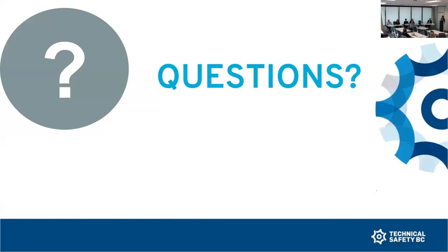So all of those are big questions. And how do you put an effective overall safety program in place so that your ventilation, your detectors, your hazard assessment, and your emergency procedures that allow or restrict entry into a space that's known to have ammonia, all of those things really need to work together. But there's a lot of questions. The acceptance criteria is a difficult one. My last comment is we do need to keep in mind that regulations and adopted codes generally and typically provide a minimum level of prescriptive requirements.